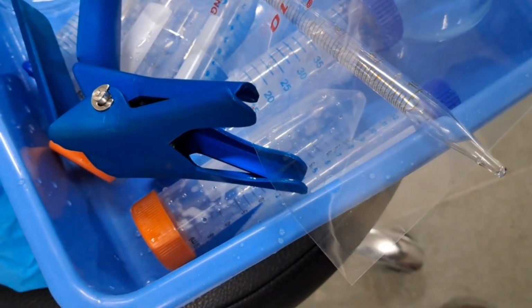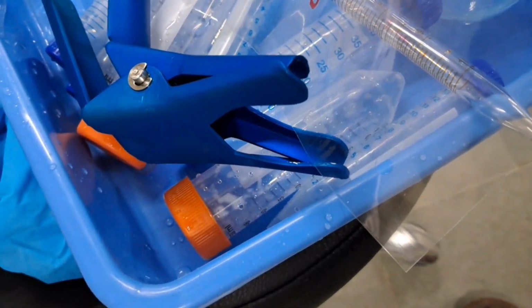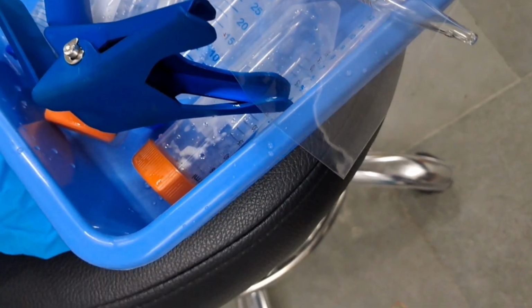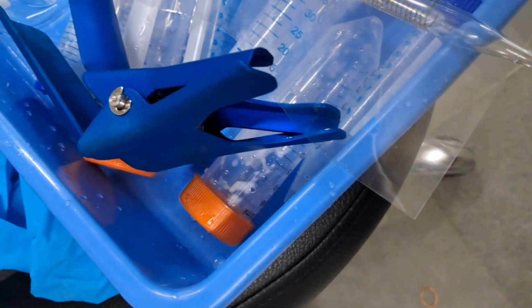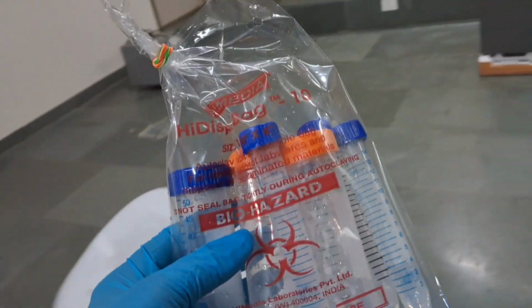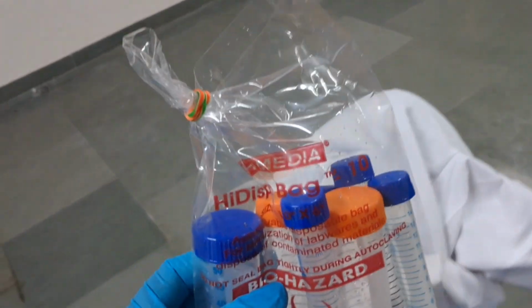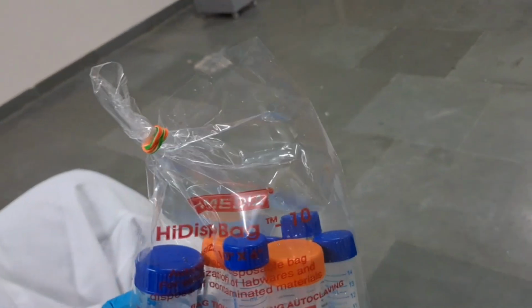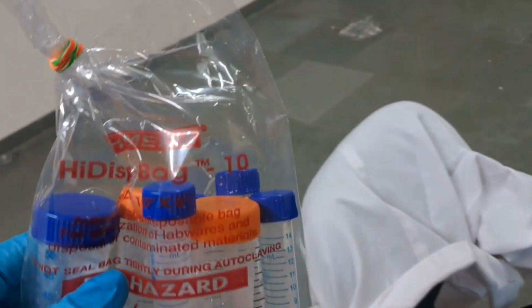You have to leave a 2 finger space, so it should not be airtight, so that the pressure can move inside. For all the labwares, the cap should be opened, and at most it should be only 30% tight. That means 70% should be open, so all the pressure can go in and out. So the easy exchange of air should be there, and you can pack the bag like this, leaving 2 or 3 fingers open, so the easy exchange of pressure can happen. And you will have to put it inside, and just switch on the instrument.